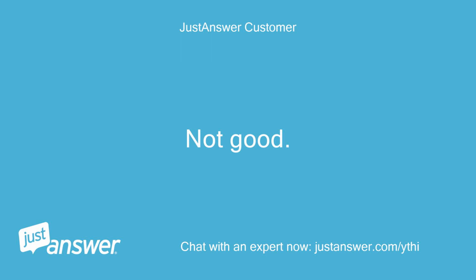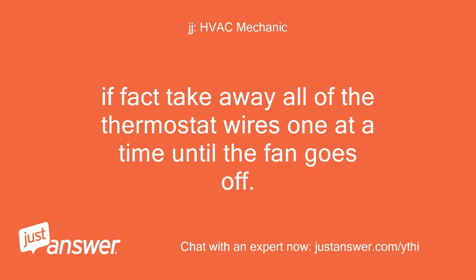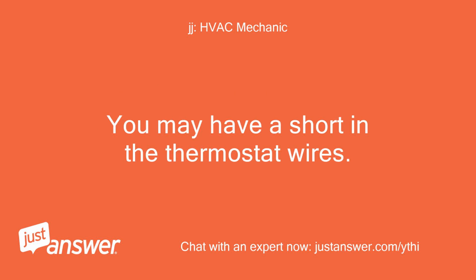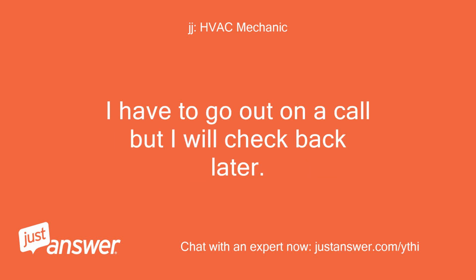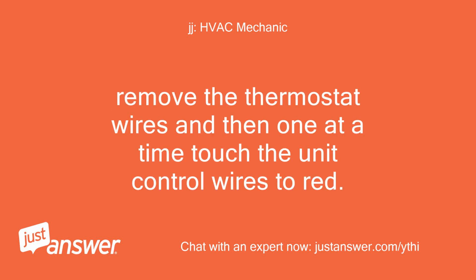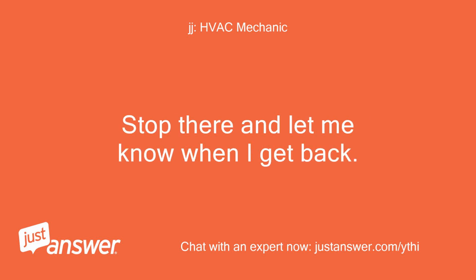Not good. Thermostat? Take away the white wire now. In fact, take away all of the thermostat wires one at a time until the fan goes off. You may have a short in the thermostat wires. Let's start with the unit and see if it works before we try to control it. I have to go out on a call, but I will check back later. Remove the thermostat wires and then one at a time touch the unit control wires to red. Green first, white second, yellow third. Stop there and let me know when I get back.